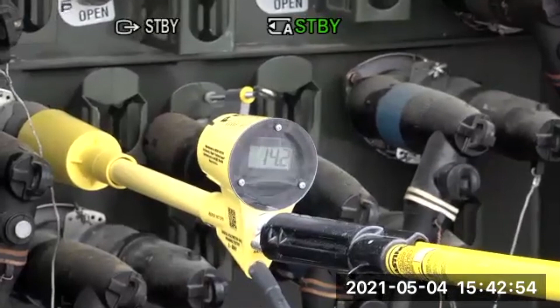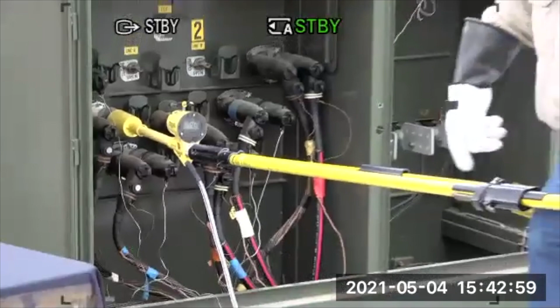All right, can you zoom in there, Parker? You can see that this 14.2 is a little higher than 13.8 because that's true RMS voltage, a little over 14,000. But the cord, you always want to make sure the guys are taught to stay away from that cord, that 36 inches as well. It's very important.